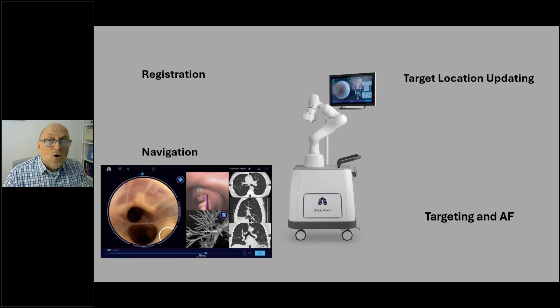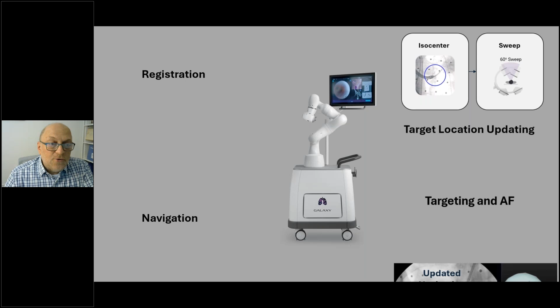Once you get into the vicinity of the nodule, then you'll do your target updating. This is done by doing a spin at isocenter, where the nodule is at isocenter. If you're doing 2D fluoro, you'll do a 60-degree sweep. This 60-degree sweep will create imaging that gets sent over to the CPU of the system. The CPU will then identify where the new target location is, and it will relate it to the tip of your scope.